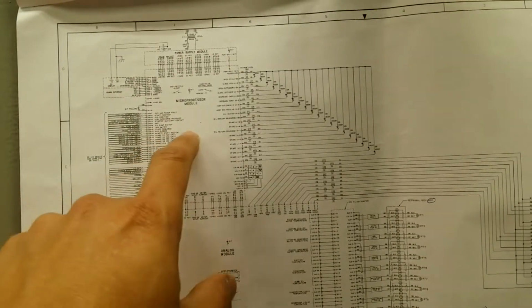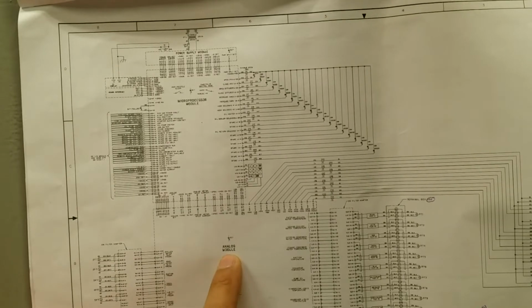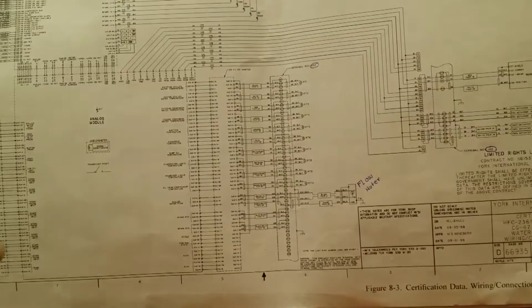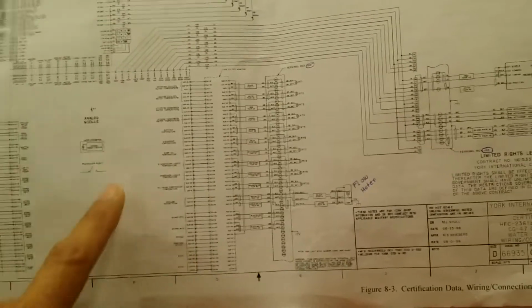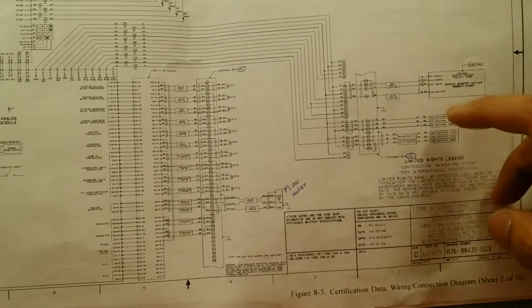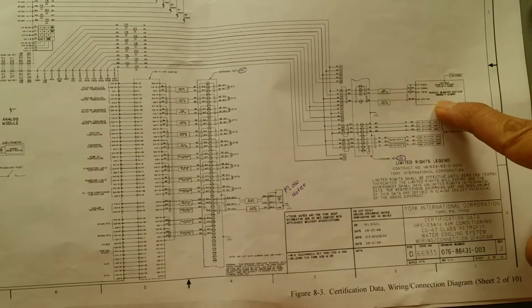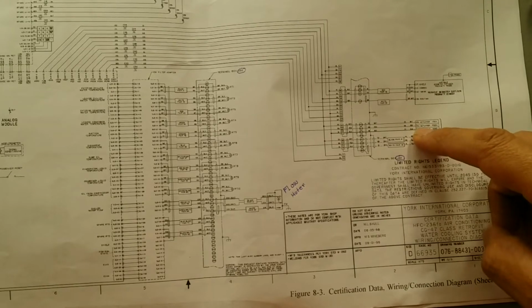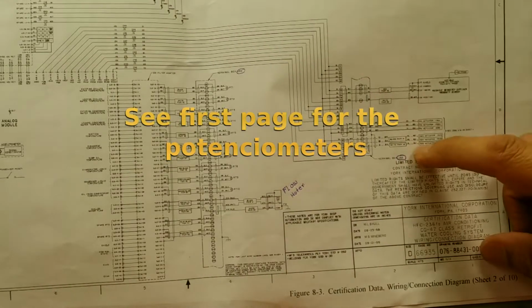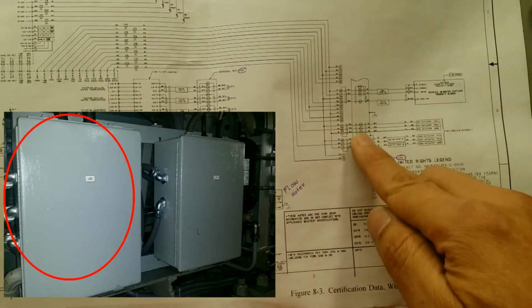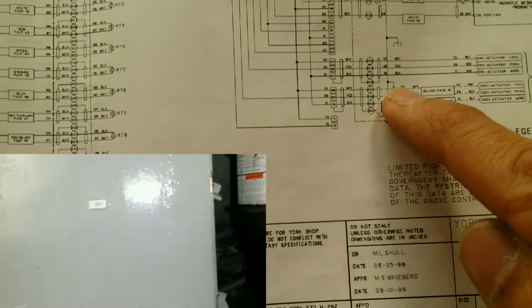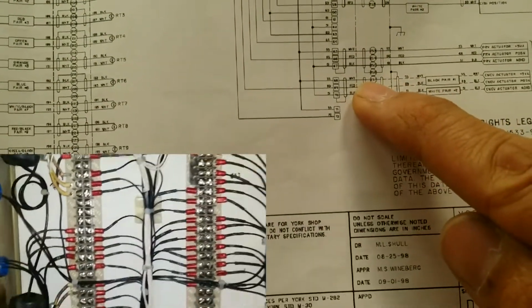The last circuit card that we haven't talked about is the analog module. This one collects a whole bunch of analog inputs: the variable diffuser, a proximity switch, and also the potentiometers that are built into the PRV actuator and the CWC valve. Luckily, there is this junction box, JB2, which you can open and just look at the actual wire numbers. You can take readings with your multimeter and read what output is coming in from those sensors.